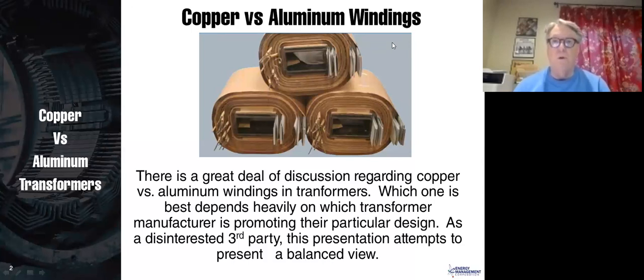It could be air-cooled, in which air flows through and cools the copper and aluminum and steel. Or it could be an oil-based transformer in which you have mineral oil or some other kind of cooling fluid. So obviously, when we talk about copper versus aluminum, we're only talking about the windings. And as a non-transformer manufacturer, but someone who uses and supplies a lot of transformers, we're going to give you a third party's view of this.